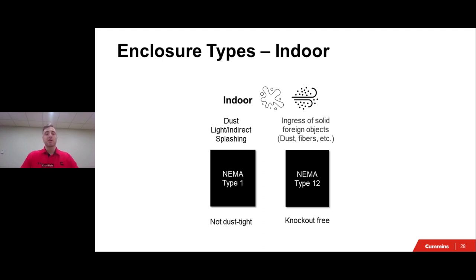This enclosure will protect against dust, light, and indirect splashing. However, note that it is not dust tight and primarily serves the purpose of protecting the switch from incidental contact. So that would be like, say, if you're in the room where your system is, protect from contact, whether that's you swinging something around or something else in the enclosure breaking down and maybe accidentally hitting it.